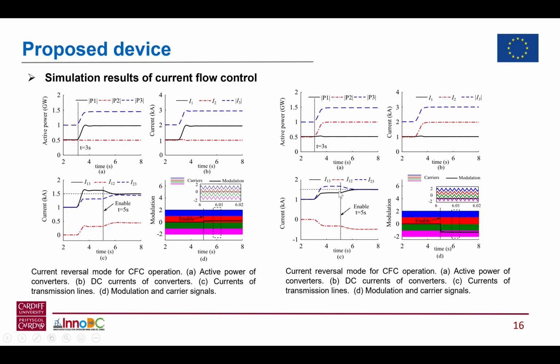And this slide shows the simulation results for the current flow control. Under these simulation conditions, the operating point is artificially changed in the simulation. At the initial stage, the current flow controller is disabled. So we can see that there are some unbalanced current flows between transmission lines, and one of the transmission lines is just beyond the current limit of 1.5 kA. At t equals 5 seconds, we enable the current flow controller. So we can see that the unbalanced current flows between transmission lines can be balanced.